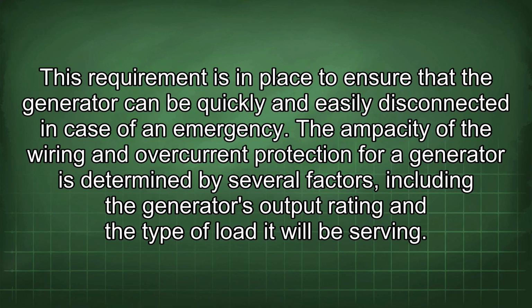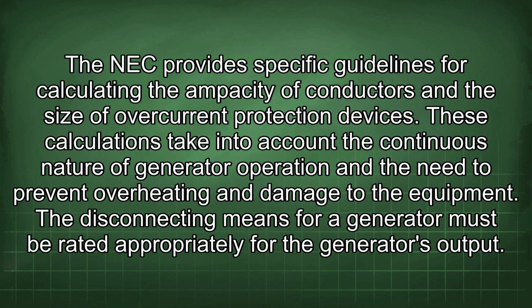The ampacity of the wiring and overcurrent protection for a generator is determined by several factors, including the generator's output rating and the type of load it will be serving. The NEC provides specific guidelines for calculating the ampacity of conductors and the size of overcurrent protection devices. These calculations take into account the continuous nature of generator operation and the need to prevent overheating and damage to the equipment.